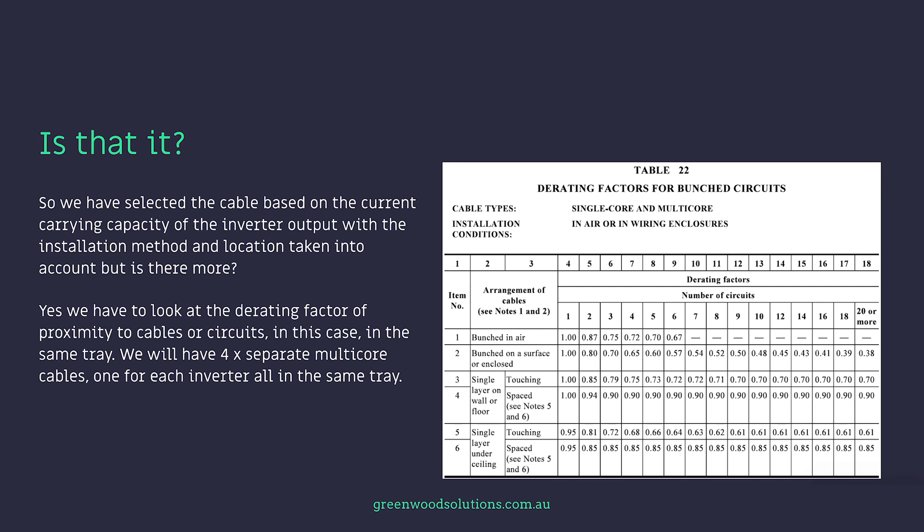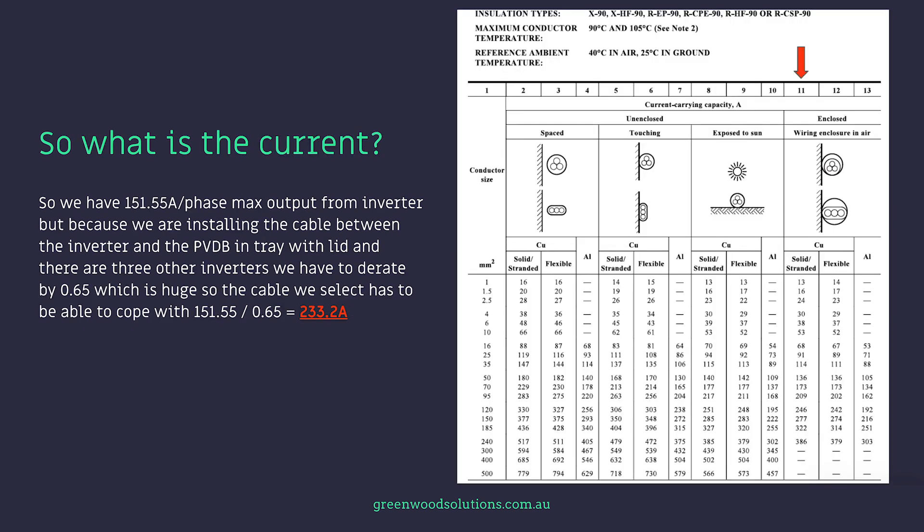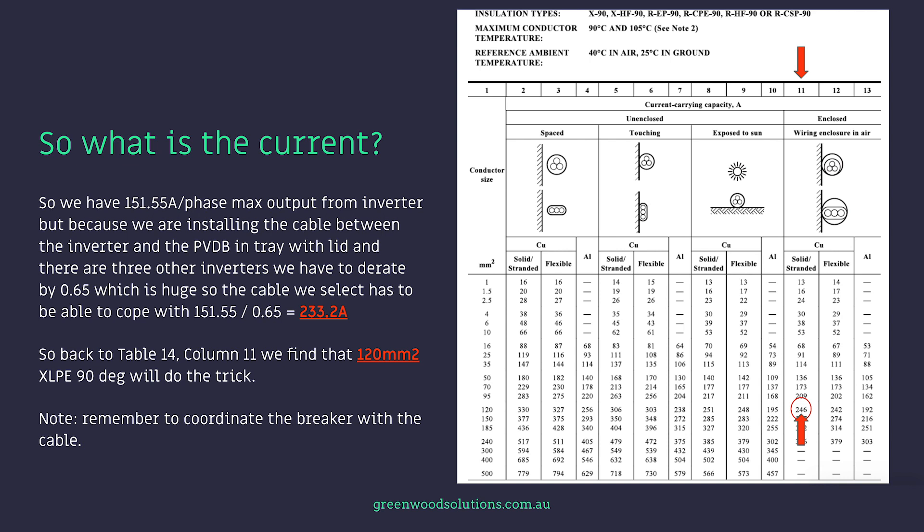We also have to look at the derating factor for proximity to other cables or circuits — in this case other cables in the same tray. We will have four separate multi-core cables, one for each inverter, all in the same tray. Looking at table 22 column 7 item 2, we find a derating factor of 0.65 because there are four inverters, each classed as a separate circuit. So the cable must cope with 151.55 amps divided by 0.65, which equals 233.2 amps. Going back to table 14 column 11, we find that 120mm² XLPE 90-degree cable will do the trick.